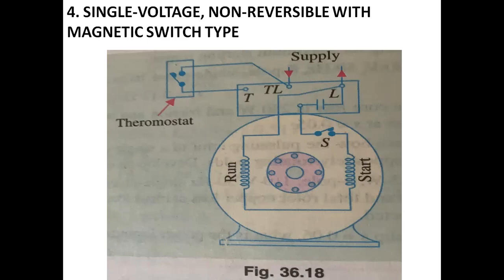One disadvantage of capacitor start motors using magnetic switch lines is that if any slight overload occurs, the plunger may operate. When the plunger operates, it reconnects the starting winding circuit to the supply. Since the starting winding is designed for only very short periods — three seconds or less — it will burn out. This is the single voltage non-reversible magnetic switch type.